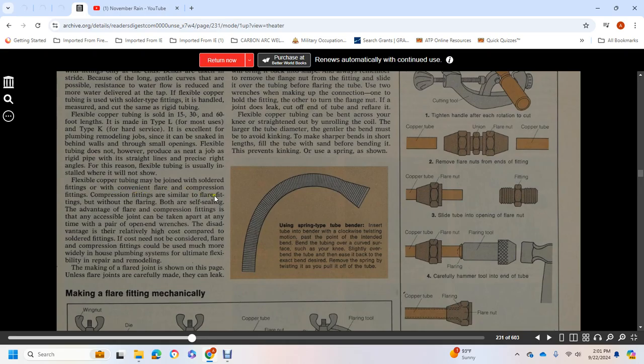Compression fittings are similar to flare fittings but without flaring, and are self-sealing. The advantage of the flare and compression fittings is that in a joint, any accessible joint can be taken out at any time and opened with wrenches. The disadvantage is the relatively high cost compared to solder fittings. If costs need not be considered, flare and compression fittings can be used much more widely in housing plumbing systems for ultimate flexibility in repair and remodeling.